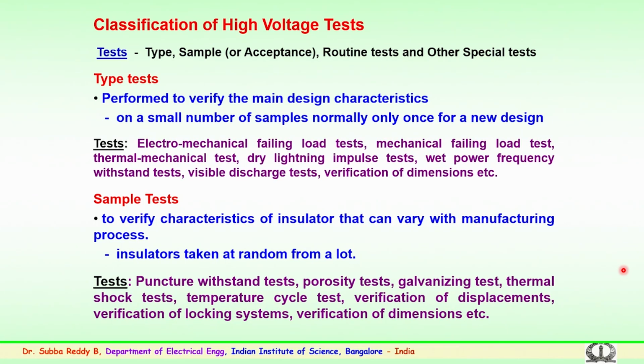So, for example, in the case of insulators, if the design remains the same for a particular voltage level and a particular creepage distance, a small number of samples from that lot are type tested in the type testing institutes or laboratories. Unless the design changes, the test need not be repeated. These type tests consist of the electromechanical failing load test, the mechanical failing load test, and the thermal mechanical test, where both thermal and mechanical loads are applied to the insulator string.